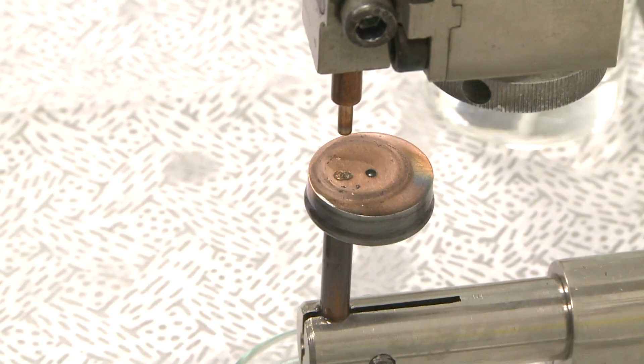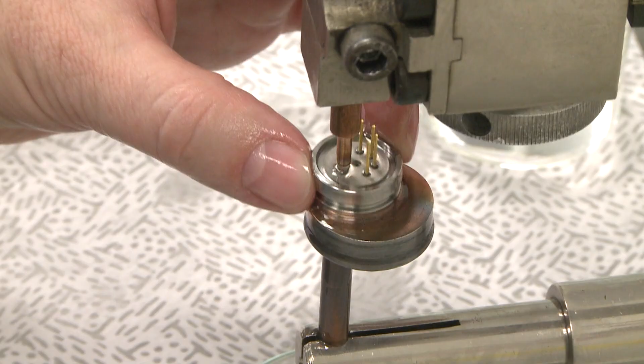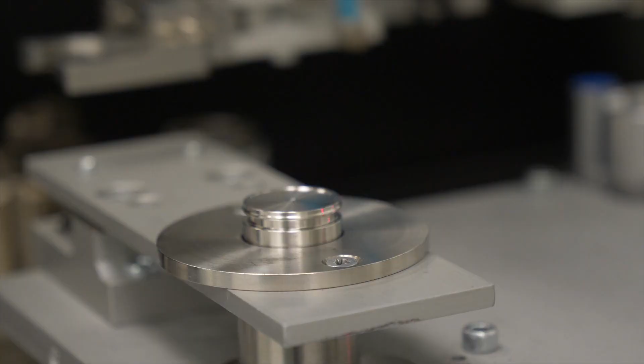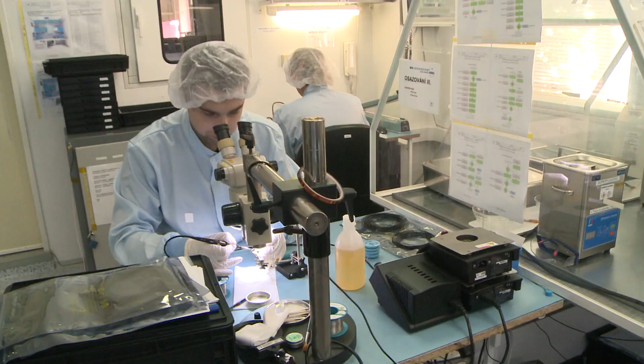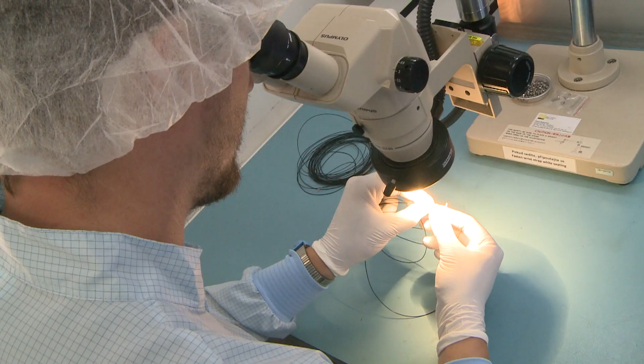The sensor's inner space is then closed by a ball, which is welded to the base using a current impulse. The parameters of all the sensors are then measured thoroughly using automatic test equipment. Measured values are then processed and attached to the serial number of individual sensors. The numbers are archived to improve linearity and reduce thermal errors.